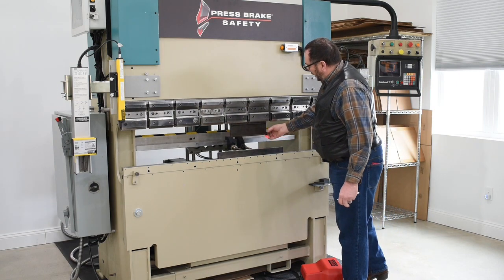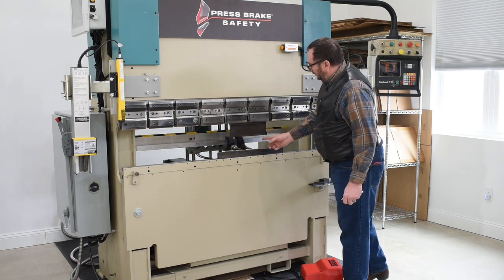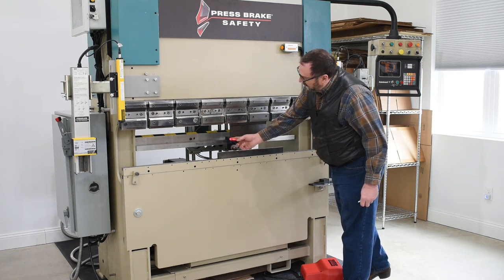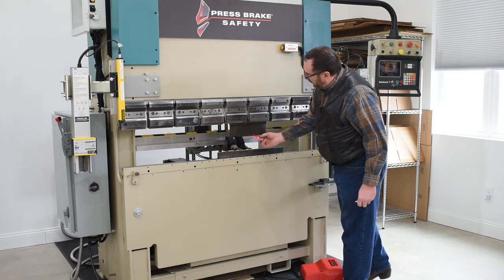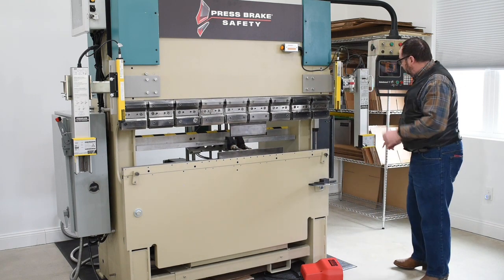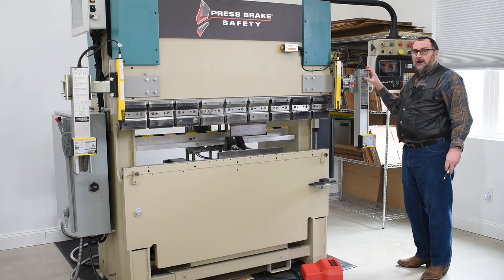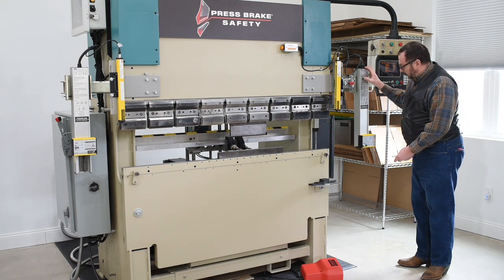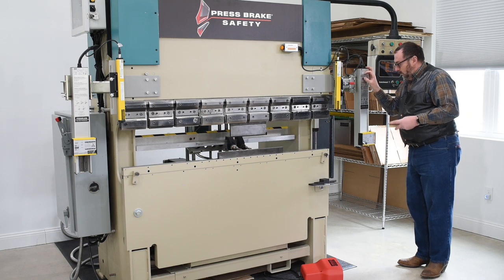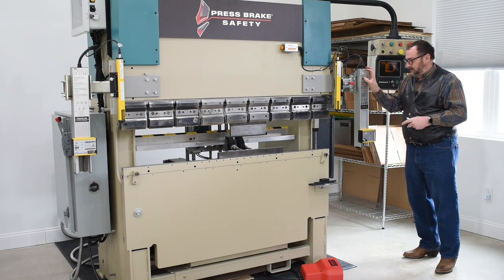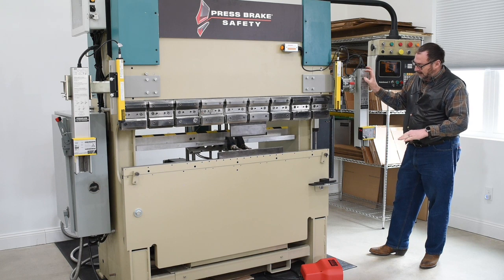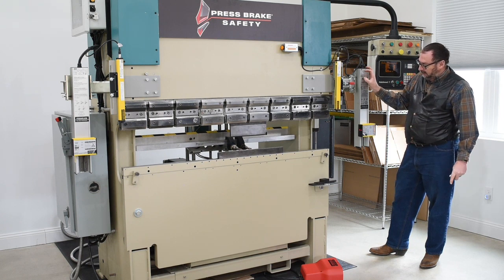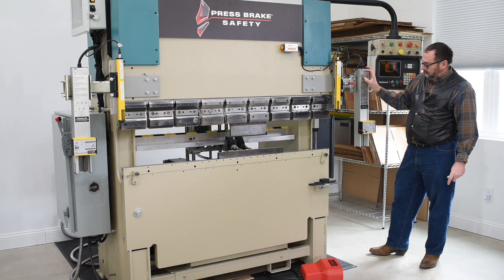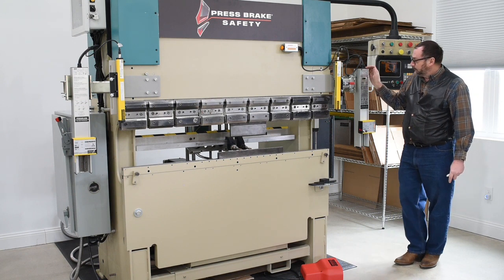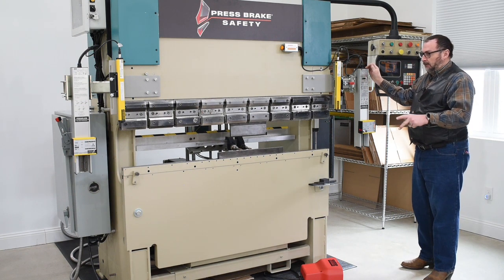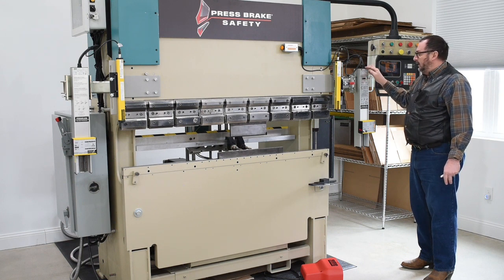I accidentally hit the magnet, so I'll reposition it. But now I've got the laser right below the tip of the upper tooling. Now, we'll push and hold the black button. This will bring the receiver upward. Once the receiver sees the transmitter, it will hesitate. When it hesitates, that's when you release the black button. Just like so. At this point, don't interrupt the laser. Just go ahead and recalibrate.